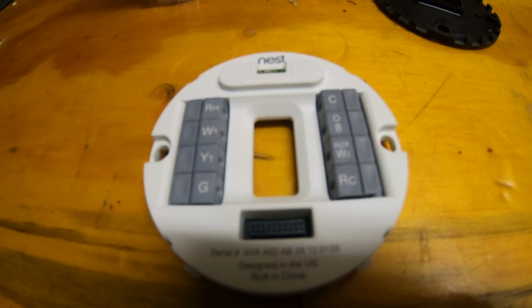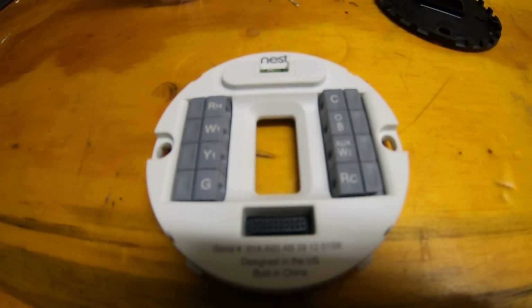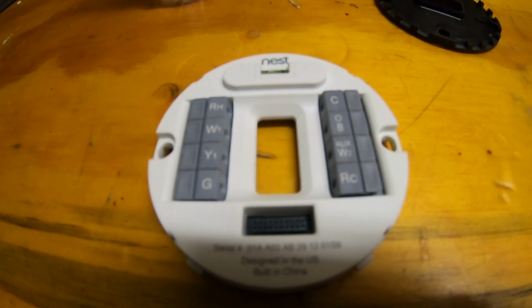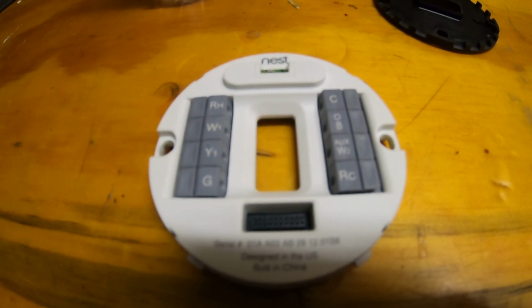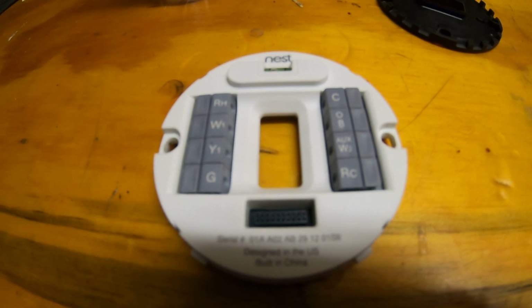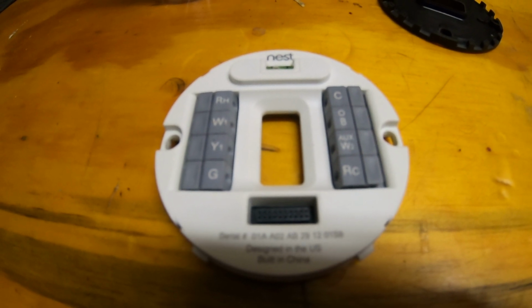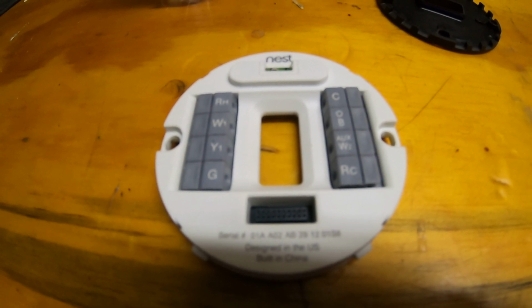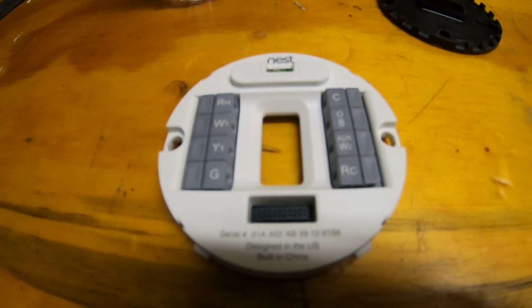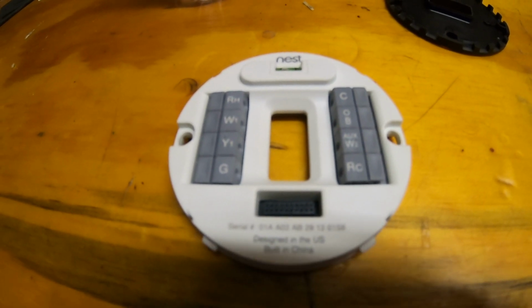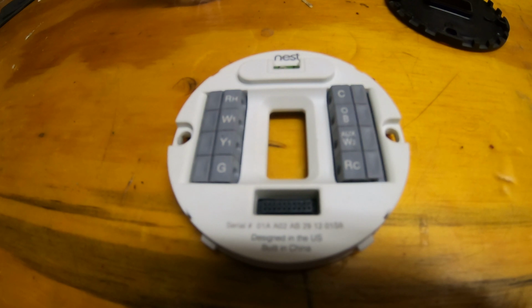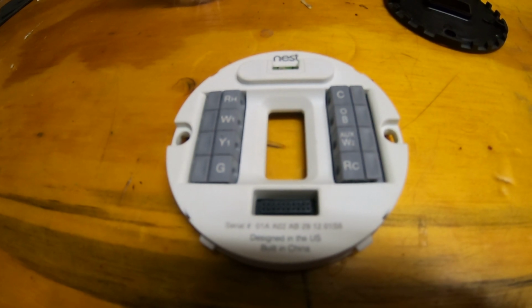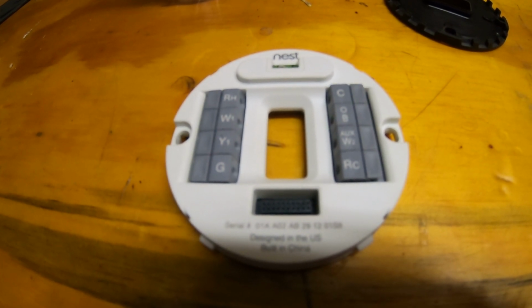I tested for 24 volts at the contactor at the outside and saw about maybe 16 or so when it was calling for cooling, and that was indicative of a problem. There was a trip breaker as well, so I wasn't getting 240 volts at the other side of the contactor on the high voltage side. So long story short, this was very difficult to troubleshoot because really from there it can only be a couple of things. It could be a bad transformer.